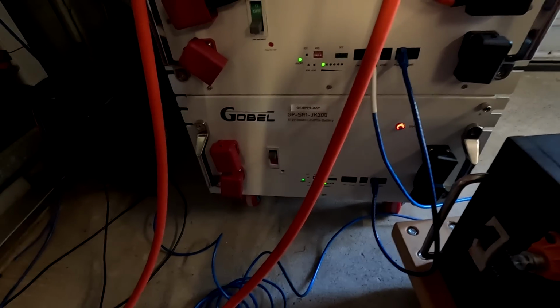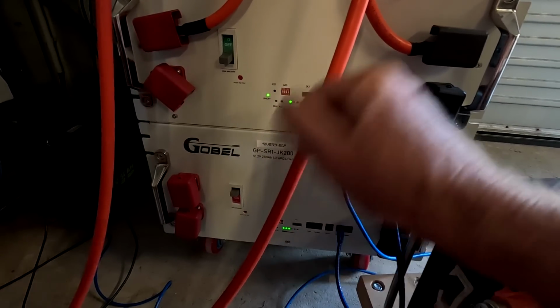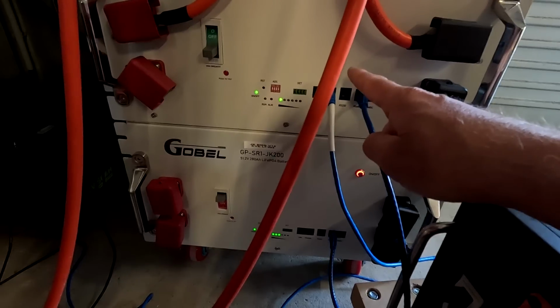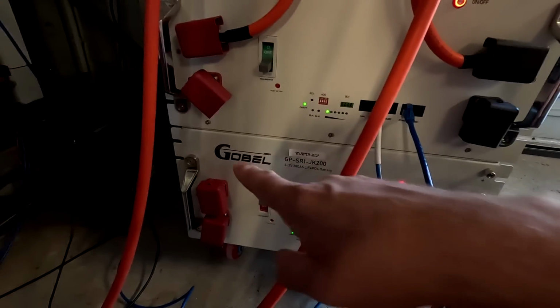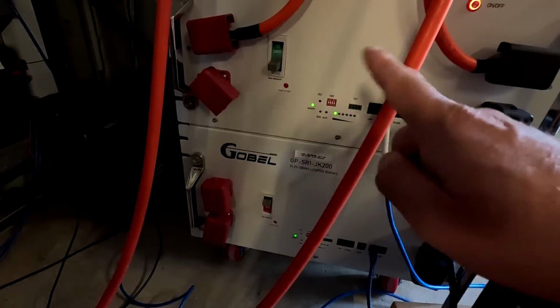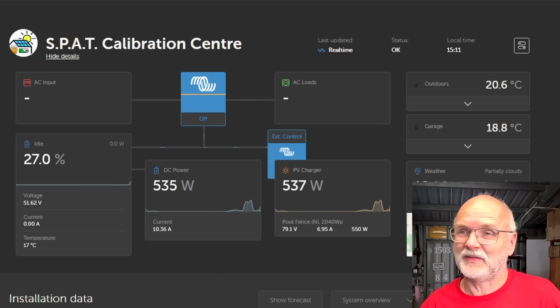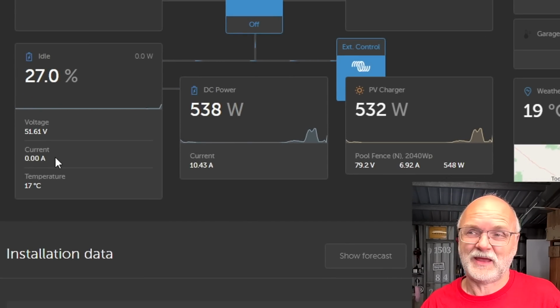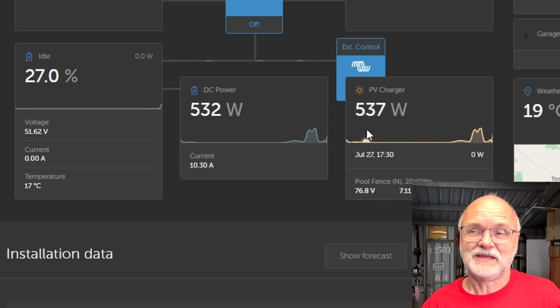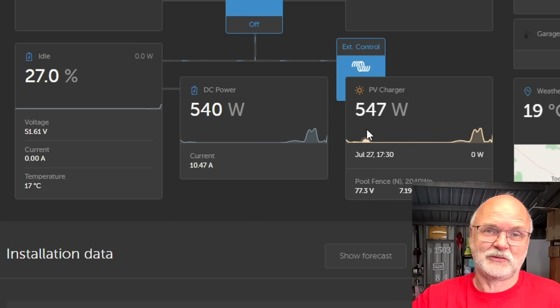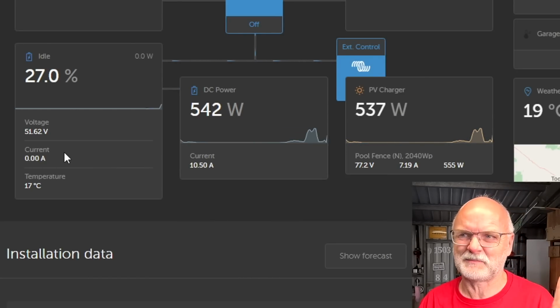Okay, let me walk you through the setup here. I've got these two JK inverter BMSs connected with a network cable. The top one is the master, the bottom one is the slave. They're not electrically connected, but that doesn't matter, we just want the communication up and running and to change some parameters to trigger some alarms in these BMSs. Because these two batteries aren't connected to anything at the moment, we don't see any current flowing into them. Even the solar charge controller thinks it's charging the batteries, but this power is actually going into the battery shelf at the moment.